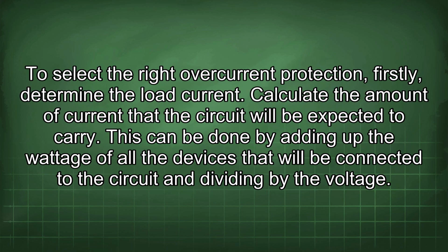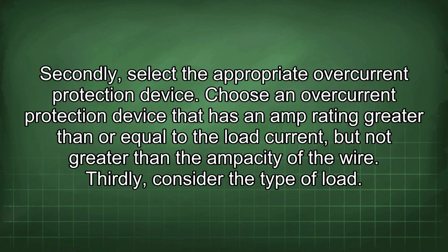To select the right overcurrent protection, firstly determine the load current. Calculate the amount of current that the circuit will be expected to carry. This can be done by adding up the wattage of all the devices that will be connected to the circuit and dividing by the voltage. Secondly, select the appropriate overcurrent protection device. Choose an overcurrent protection device that has an amp rating greater than or equal to the load current, but not greater than the ampacity of the wire.